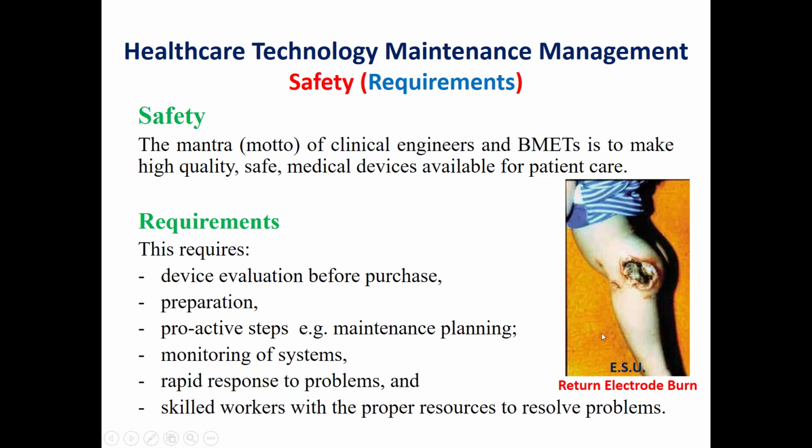Also, in this photo, we see another serious injury for an infant, which was caused by the use of a reusable return electrode for an electrosurgical unit. So the use of medical devices sometimes could lead to a serious injury or even to the death of a patient.